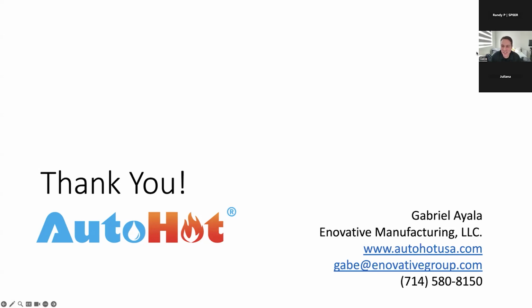Another question, Juliana is typing an answer, but it says, is an electric tankless comparable with a gas tankless? Comparable in what way? Efficiency? The answer is annual costs. The answer is that electric resistance is higher efficiency than any gas because with gas you're going to have combustion losses. With electric, you don't have any of those combustion losses. With a tankless electric, you also don't have any standby losses, so it is going to be more efficient. However, the cost is going to be much, much higher on a per energy unit basis.